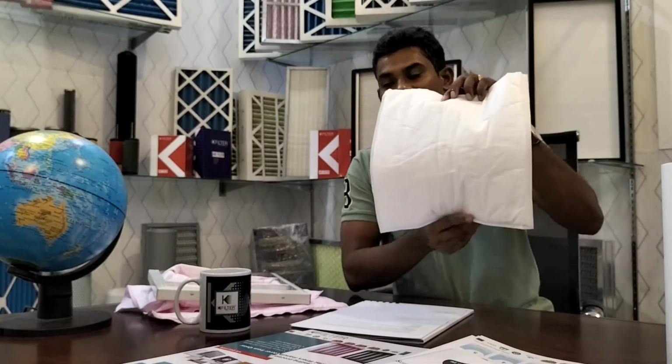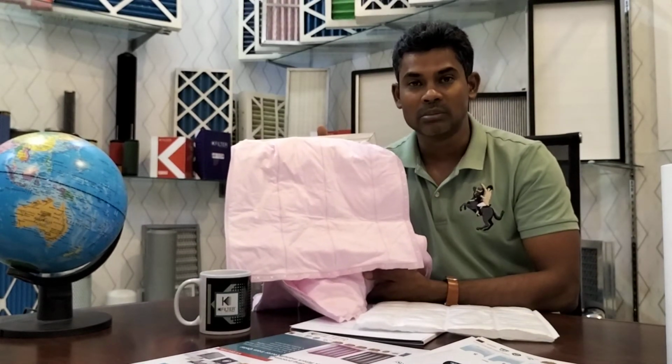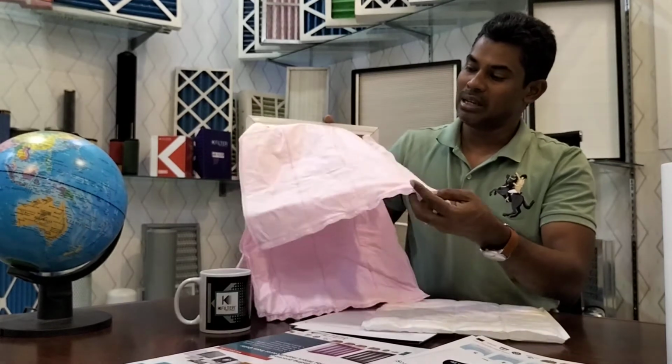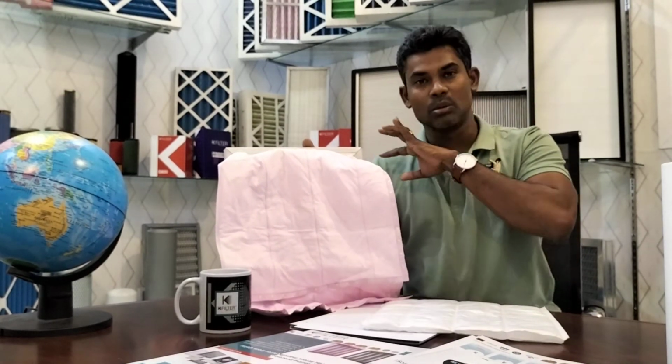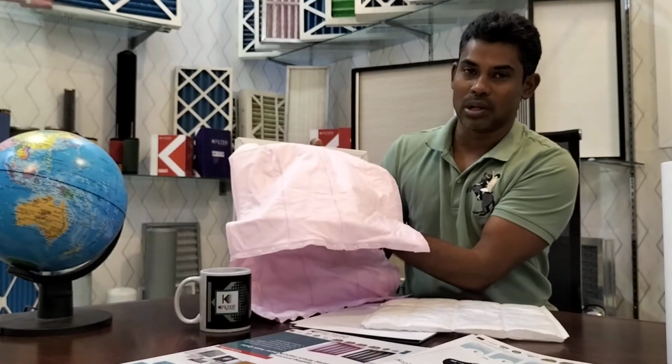So if you are not properly washing the pre-filters, all the dust will accumulate on your pre-filter section. The pre-filter will be blocked, and then the bag also, because the bag cannot get much flow, so all the bags will collapse like this. If you are not doing the periodic annual AMCs, the dust is already there, and when you clean the pre-filters, suddenly much more flow will come.